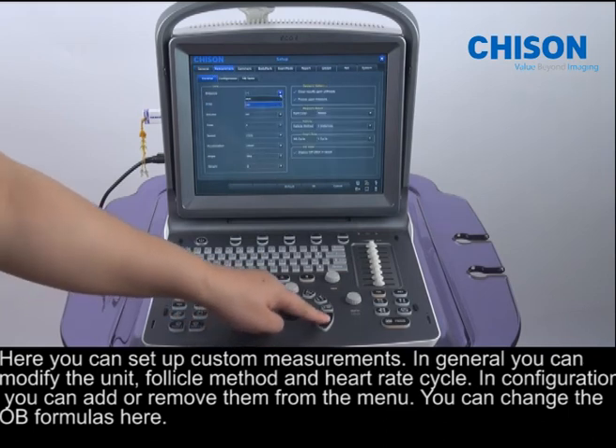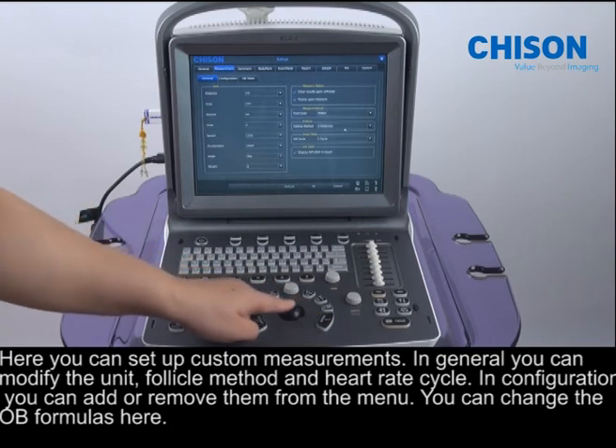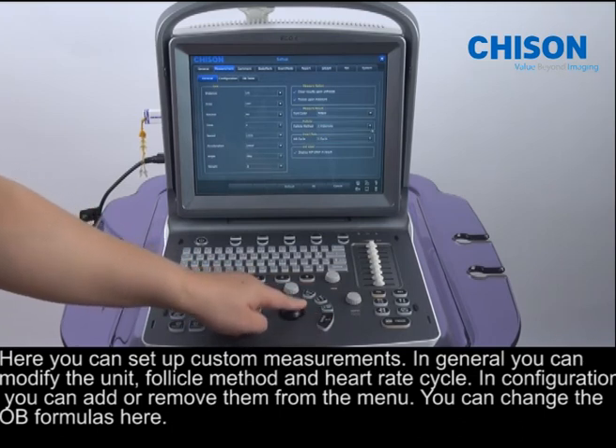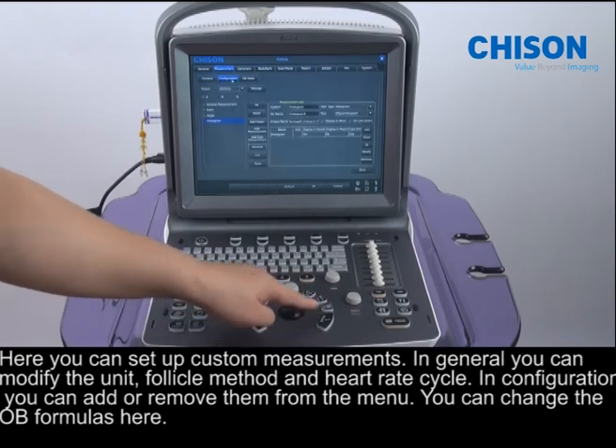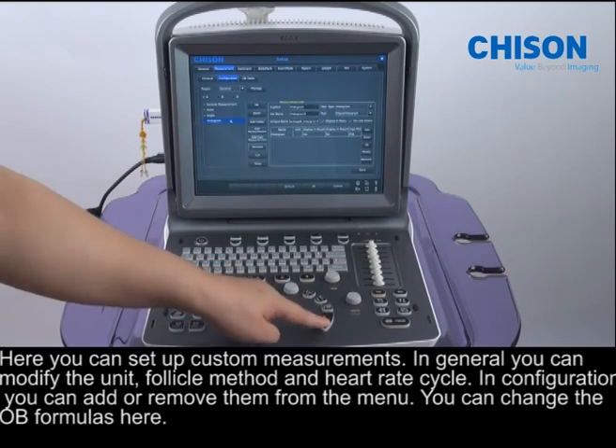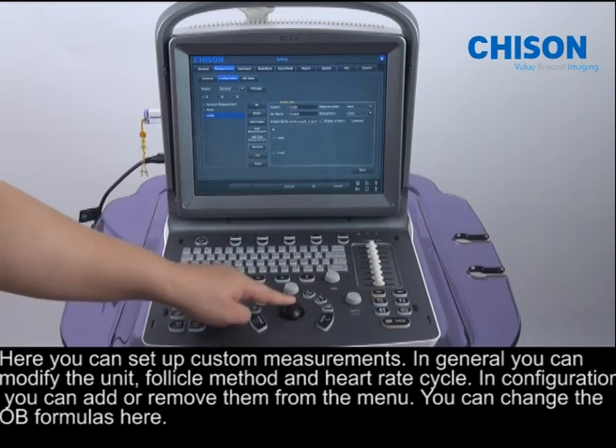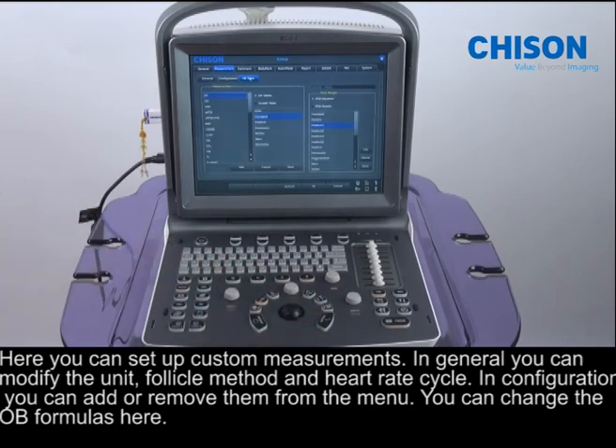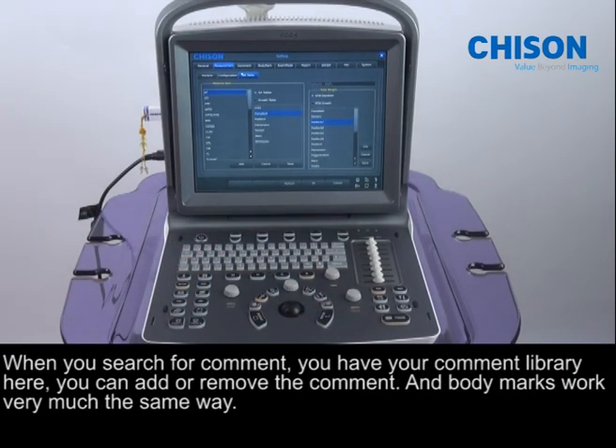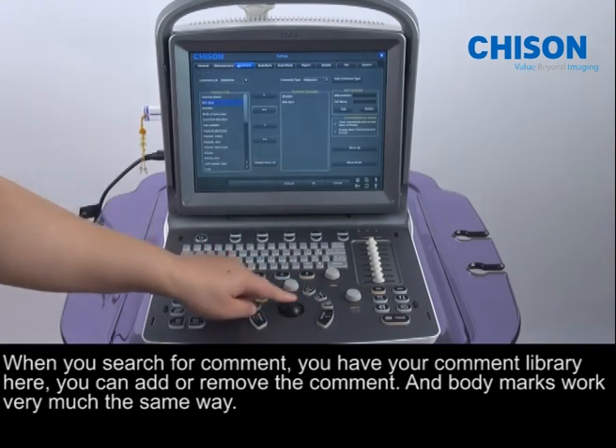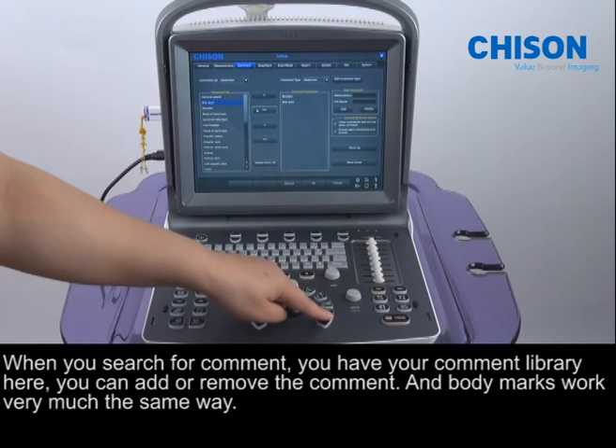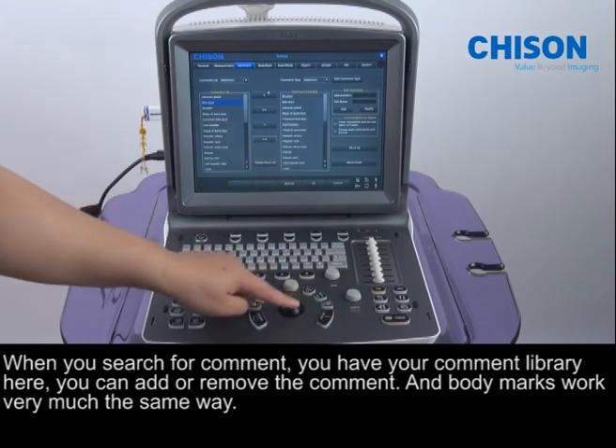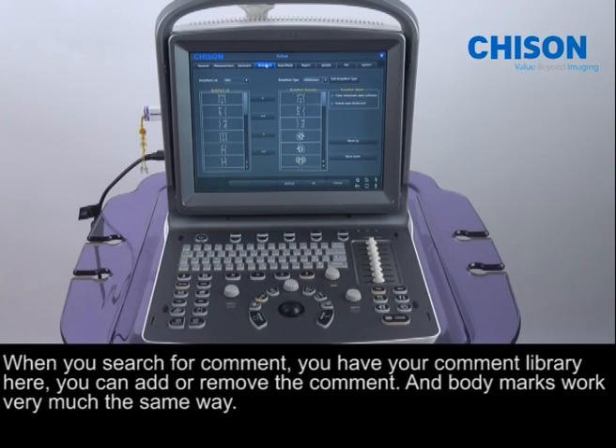In general, you can modify the unit, follicle method, and the heart rate cycle. In configuration, you can add or remove them from the menu. In OB table, you can change the OB formulas here. When you search for comment, you have your comment library here. You can add or remove the comment. And the body marks work very much the same way.